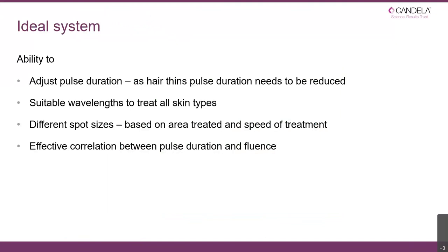The ideal system needs to have the ability to adjust the pulse duration. As already mentioned, if we're treating thick hair we need longer pulses, and if we're treating thinner hair we need shorter pulses. Additionally, as you move through the first, second, third, and subsequent treatments, the hair will start to become thinner. A very thick coarse hair after the first treatment may by treatment four be significantly thinner — at which stage you need the ability to reduce your pulse duration so you're still keeping enough heat in the target to destroy it, rather than the heat diffusing into surrounding tissue over such a long period that you never reach the critical temperature.